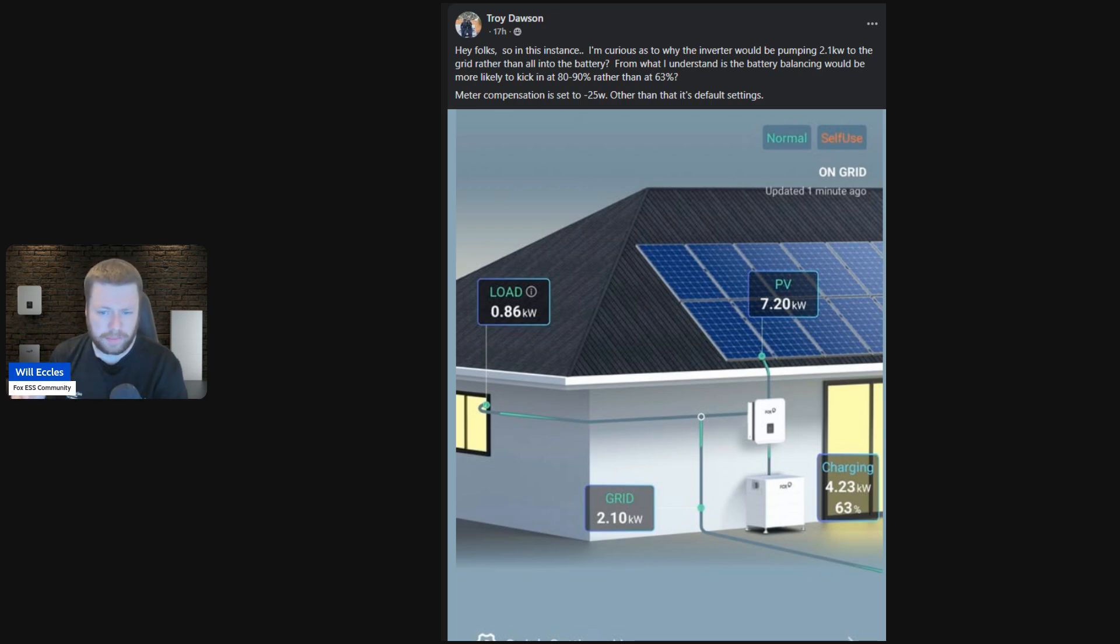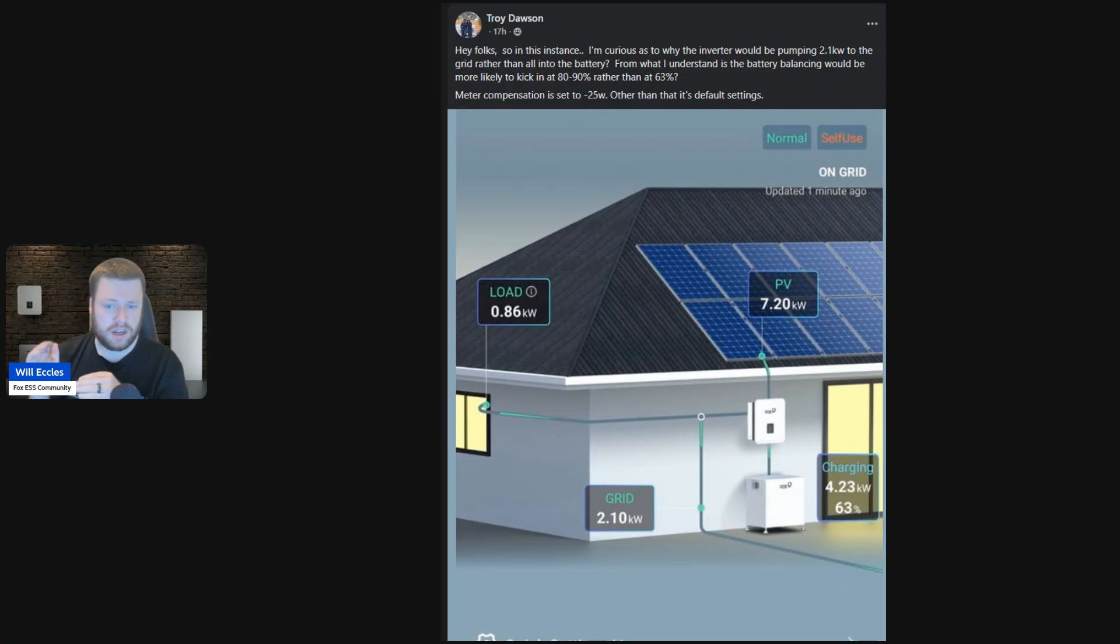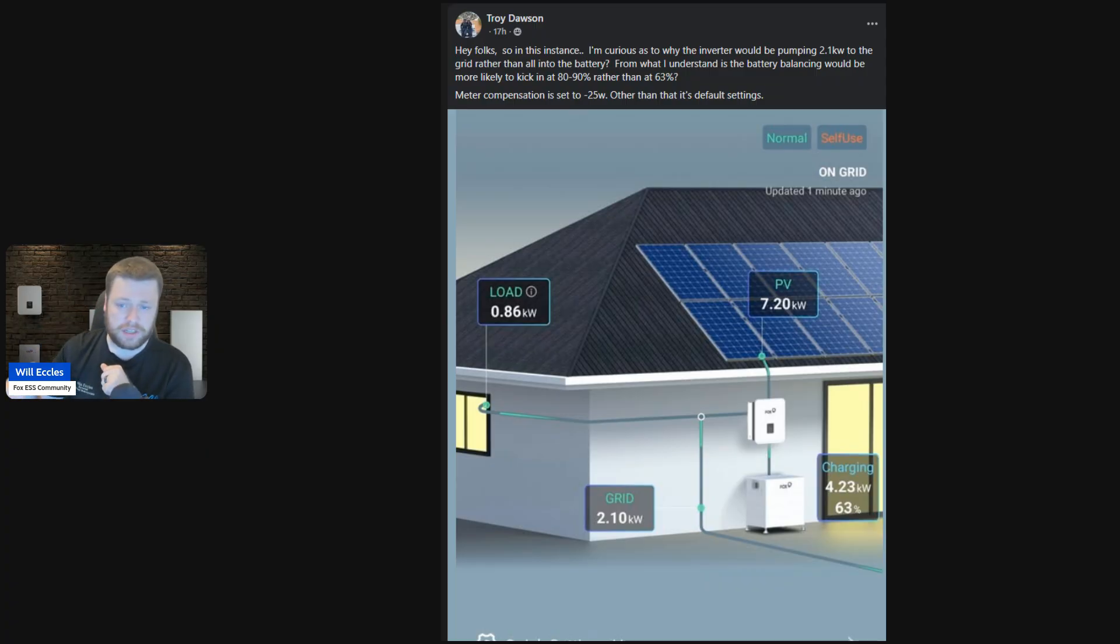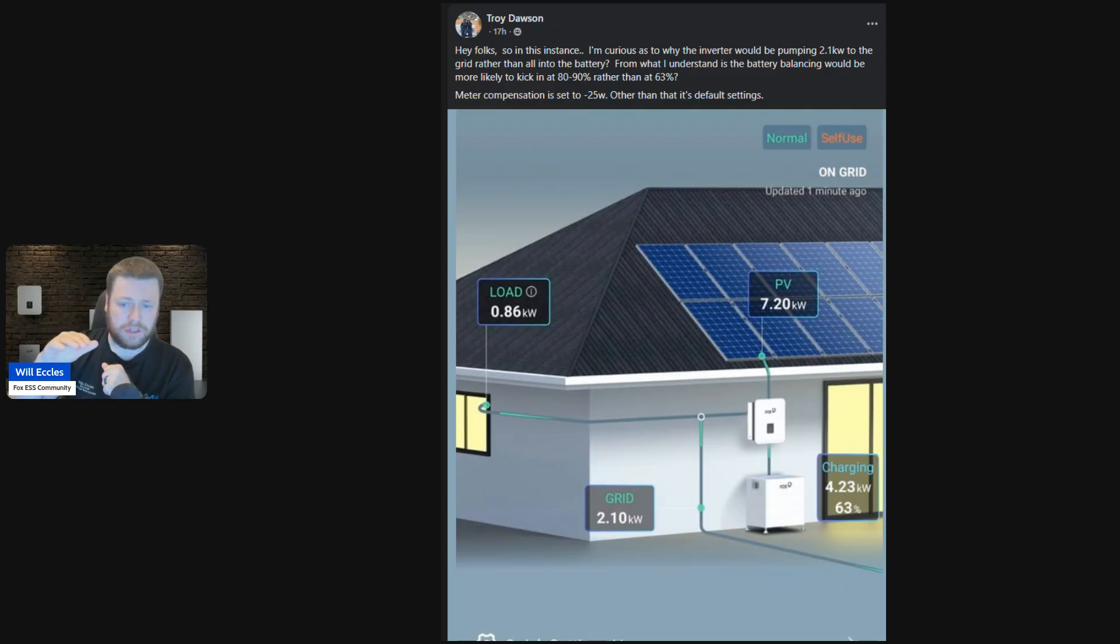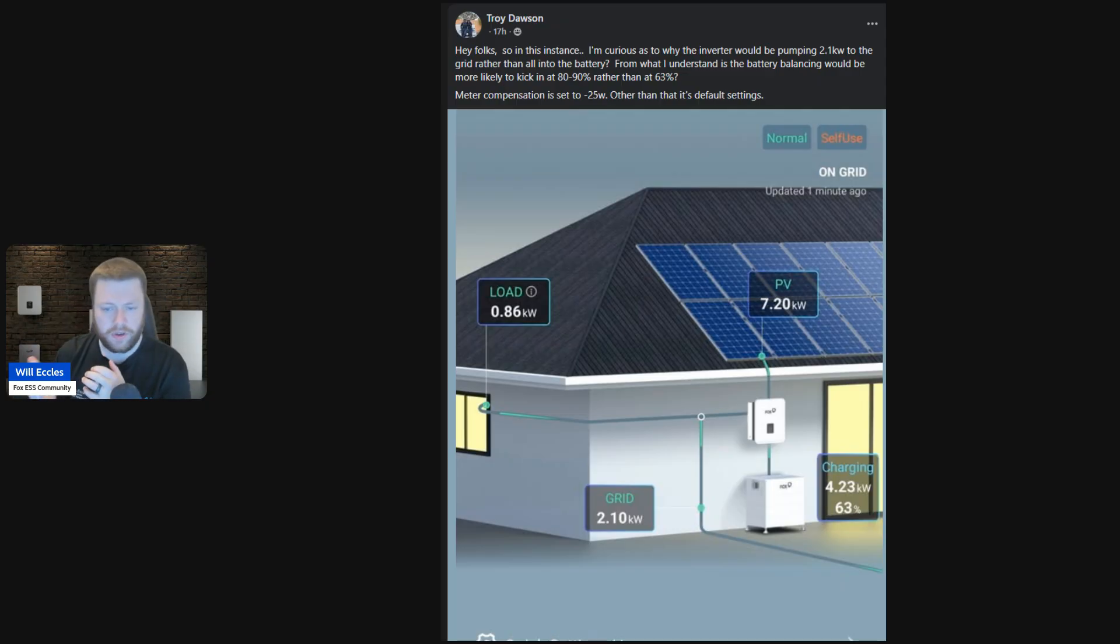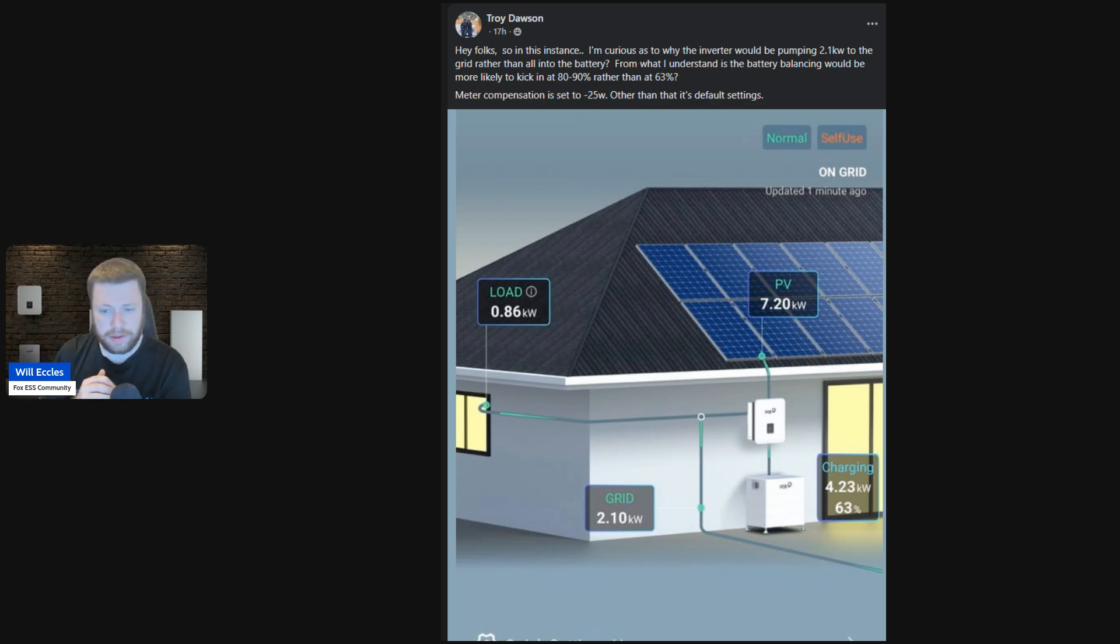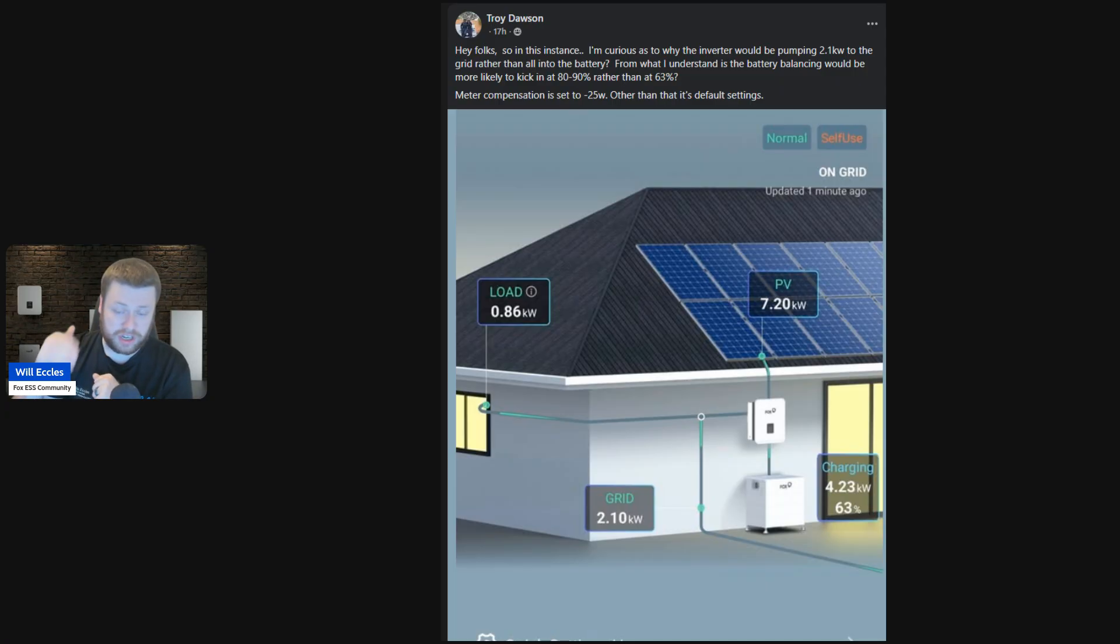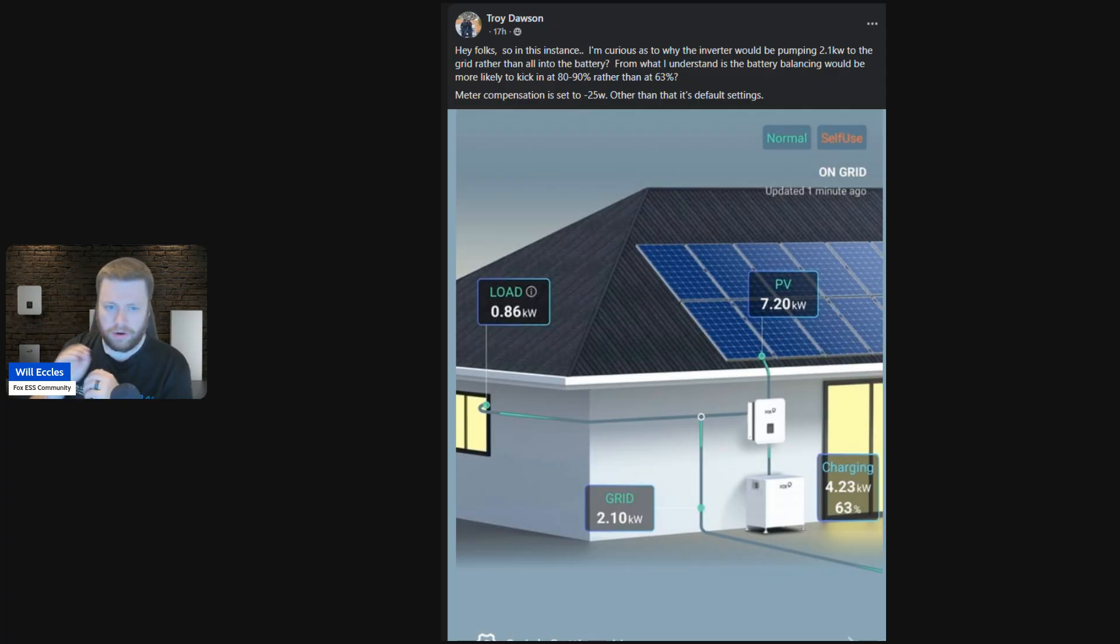The great thing about a Fox inverter is it doesn't start clipping the PV production unless you've got an export limit set. It just tries to charge the battery as fast as possible, and then subject to no other limits such as an export limit, it allows the surplus generation to flow as export. If you have an export limit turned on, then it will stop and then it will start to clip. If you have no export limit, you'll notice that it will try and charge the battery, and then any additional generation will just start to get clipped. You can see that normally on the graph.